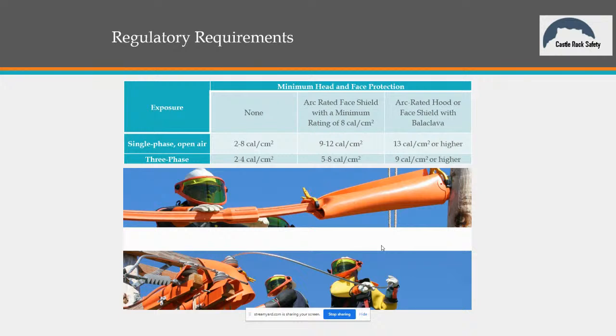What they came up with, and it's more complicated than what I'm trying to get across here, is if I'm exposed single phase open air, which you would be on a distribution line, then I'm not required to wear a face shield until I exceed 8 calories. And if it's determined to be a 3-phase event, then it's 4 calories. But typically it's going to be that single phase open air, so I'm not required to put a face shield on the utility side until I exceed 8 calories.